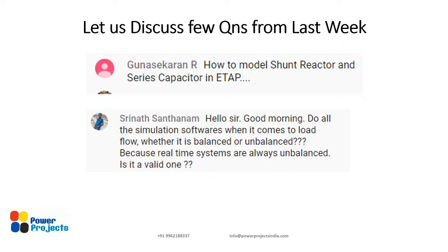Hope that answered the question of Srinath. Yes, we need to do unbalanced power systems as an unbalanced load flow only, but unfortunately, due to time constraints, modeling constraints or the effort needed, we are not really modeling it as an unbalanced load flow. Most of the time we settle for a balanced load flow. But if you go with single phase systems, or with traction where you have a heavy unbalance, it is absolutely mandatory to do the unbalanced load flow.